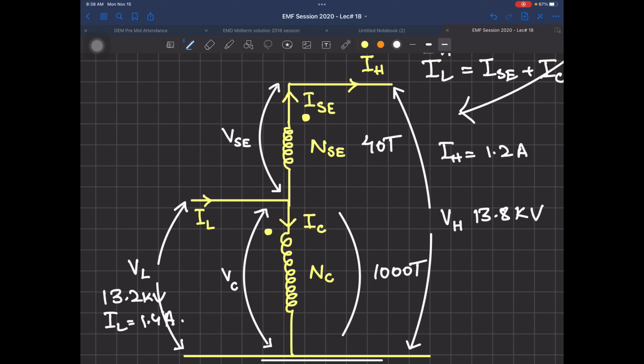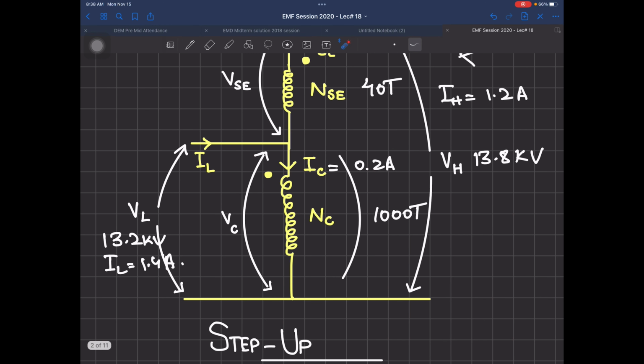Now can anyone tell me, if this is 1.4 and this is 1.2, what should be the rating of the common winding current? 0.2. So this tells you that this current is 0.2, so practically this common winding can be a very thin wire.